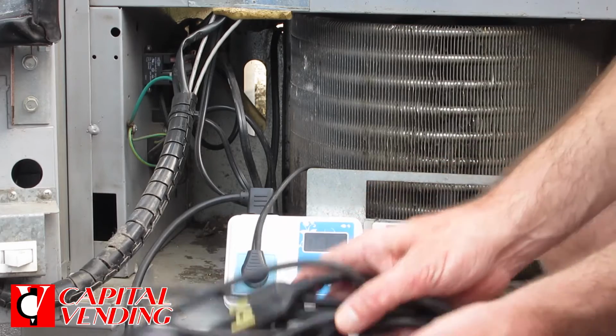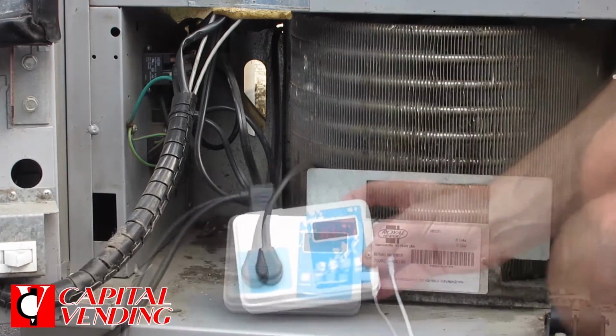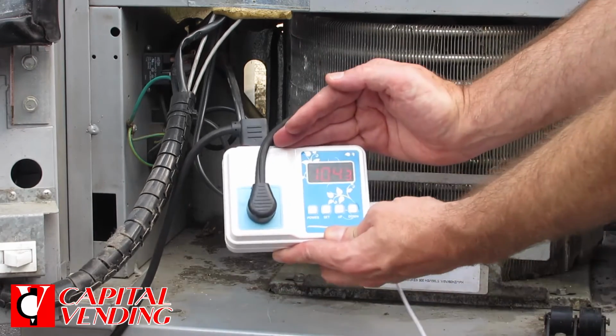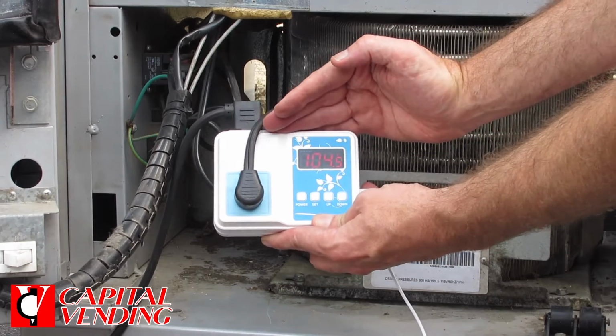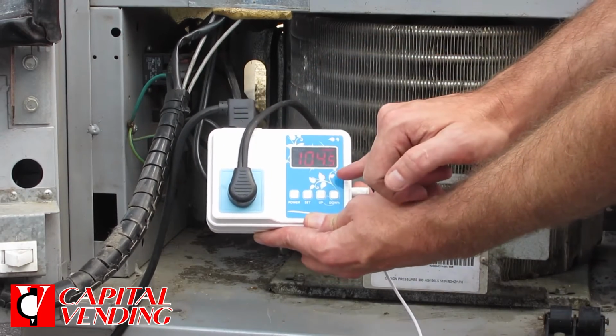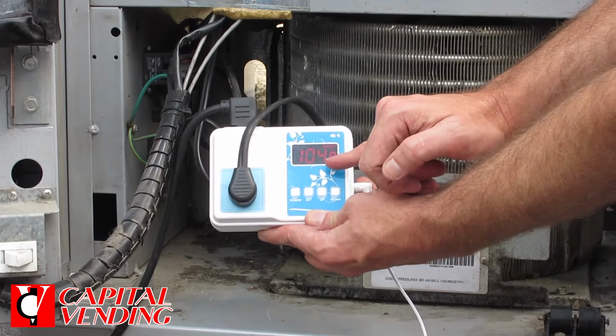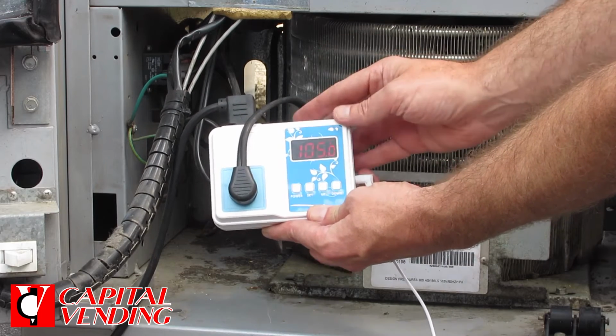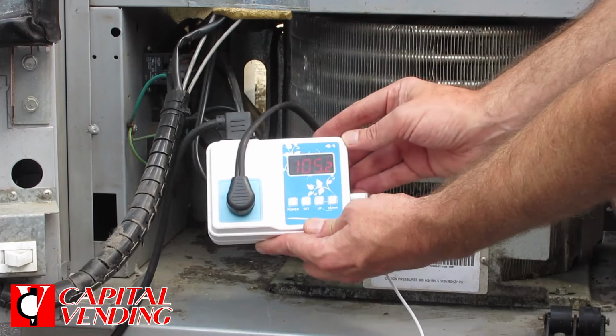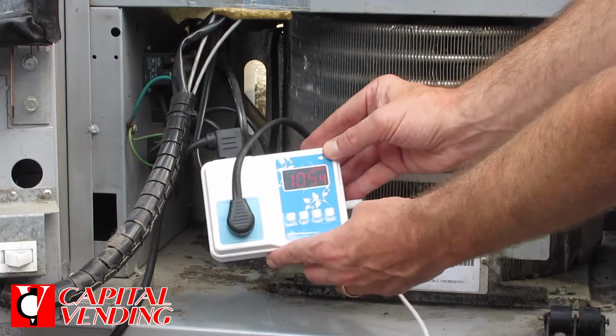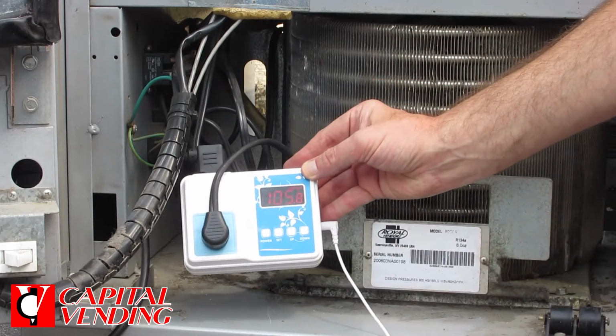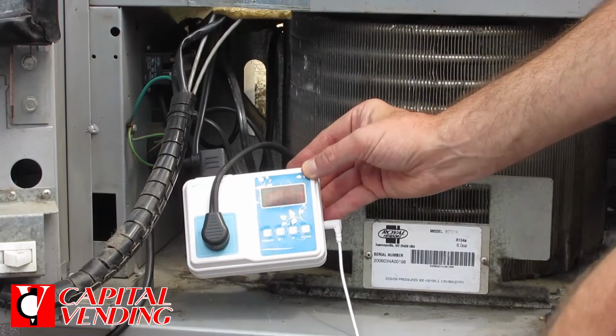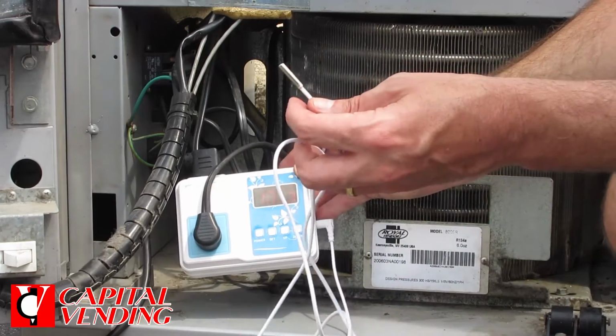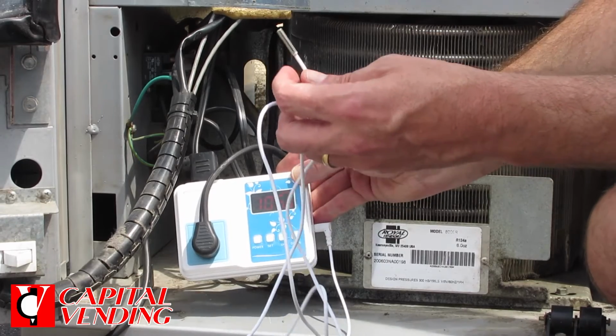I'm going to go ahead and plug this in, and you'll see the display come up. At this point—and this is true—it's 104 degrees where I'm working, outside in August, and this is showing the temperature probe reading 104 degrees. So when I plug this in directly, the compressor turns on. The other thing you need to be aware of is this has a very long temperature probe, so it could be used in refrigerated machines as well as soda machines.